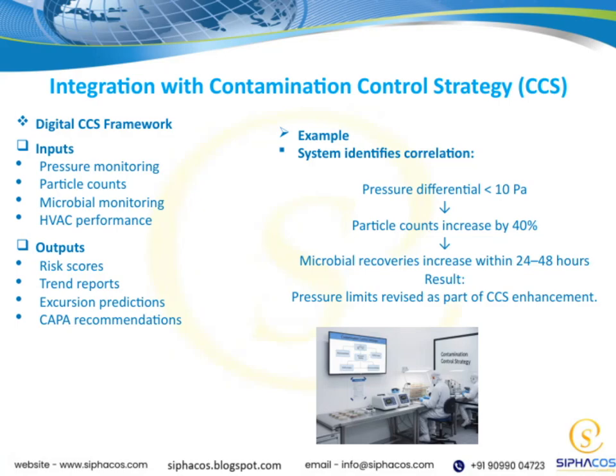Let's look at how integration with the contamination control strategy works in practice. The system spots a clear pattern: when the pressure differential drops below 10 pascals, particle counts jump by 40%, followed by an increase in microbial recoveries within 1 to 2 days. This insight leads to revising pressure limits, strengthening the overall contamination control. The digital framework pulls data from pressure, particle, and microbial monitoring, plus HVAC performance. It then generates risk scores, trend reports, predicts excursions, and suggests corrective actions. This is how data drives smarter contamination control.